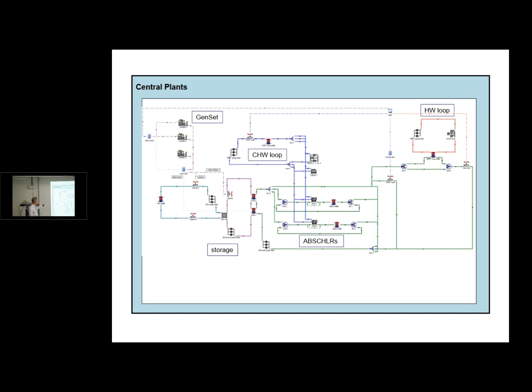The idea, generally speaking, is to take most of the stack exhaust off of these things and pass it into a storage loop, run this storage, and then when they could, run cooling from these absorption chillers, and when they didn't have enough hot water to run these absorption chillers, they've got some more traditional electric chillers running in the background that they can ramp up to meet their cooling load for this campus of buildings. And then also, if there was excess hot water available based on how they were running these generators, that could be used to supplement a boiler loop providing heating to campus buildings.